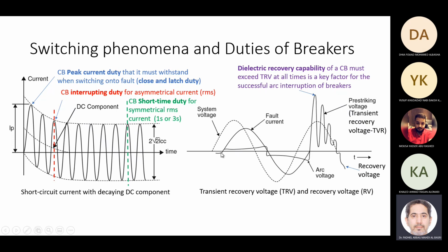While it's trying to open, it is physically open, but you still have an arc, and the arc creates a voltage drop across the contacts. When the arc is extinguished, the voltage will shoot up and down until it settles. This voltage is called the transient recovery voltage, and it depends on the circuit, whether it is a capacitive circuit you are trying to open, or inductive, the X/R ratio. There are many parameters that decide the shape of this voltage. So I have to look at this maximum voltage.